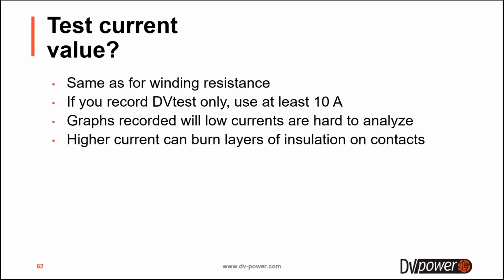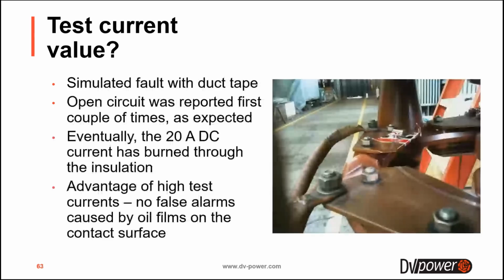Another benefit of using higher current is that it can burn layers of insulation on stationary contacts, so that those layers can develop as time goes by, especially on those tap positions that are not often used in the transformer life. So if you know the transformer and the tap changer, usually when it is online, it operates in just a few taps. So all other taps are probably never used. So you can have some layers of insulation on those contacts.